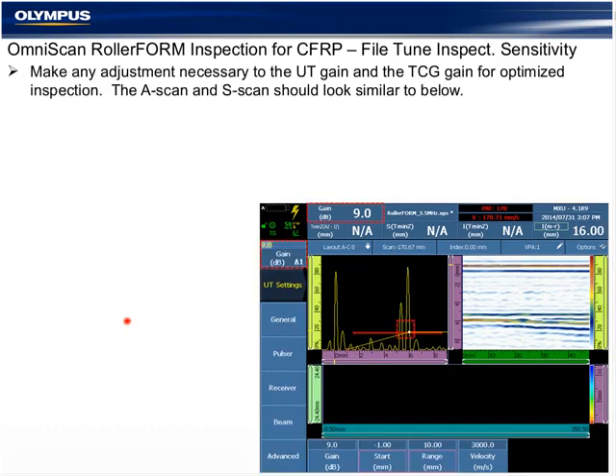We're going to fine-tune our gain a little bit, which will mean adjusting the TCG point directly over the back wall of the new component's thickness and raising and lowering the gain. We're going to make a hardware gain adjustment, or general gain adjustment, that will raise and lower both of these. And I'll make a TCG gain adjustment in the same spot that we saw earlier, just to try and maximize this signal here.